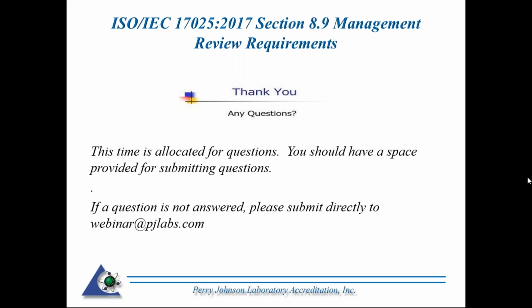If you don't have a chance to perform an audit at the customer, is there an alternative to reach the same objective? I guess what you're telling me there, and I apologize if I'm not understanding exactly what the question is, it was sort of talking about when you do work at your customer site that you should audit that. If you can't actually go out to the customer site, perhaps some organizations may cover a large area doing on-site calibration. You want to do at least a verification of that work, i.e., you want to pull up a report that was done on site. From that report, you want to look at the individual that did it.